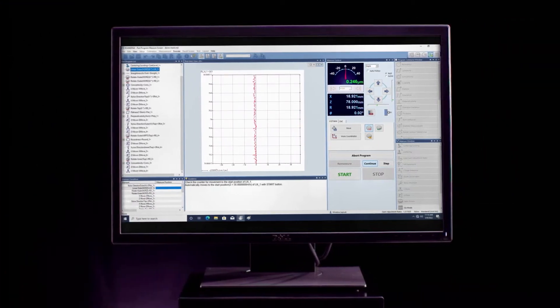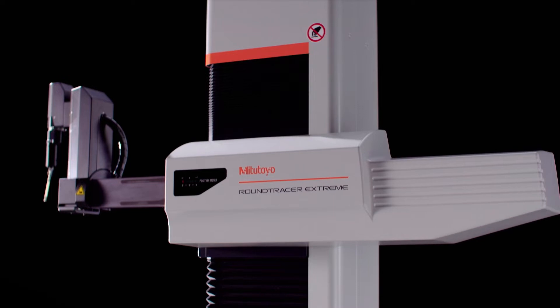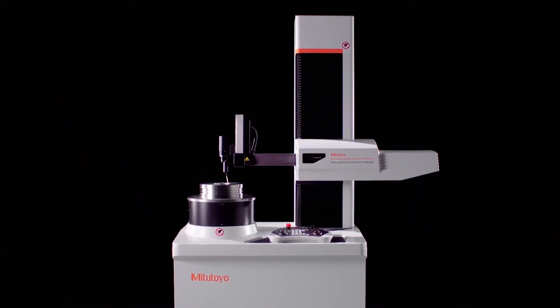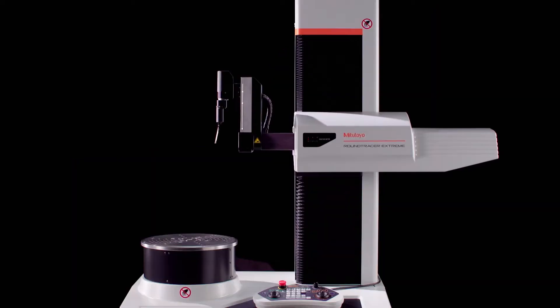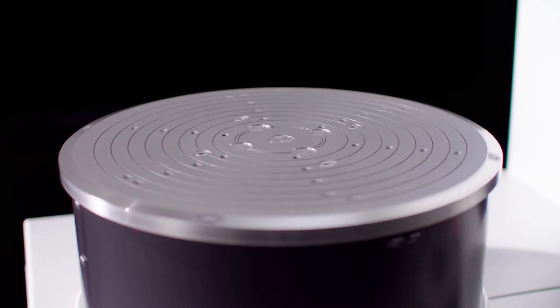Measurements of outside diameters and small holes are efficiently measured. The RTX Round Tracer Extreme features best-in-class positioning speeds with a maximum drive speed of 100 millimeters per second in both the column Z axis and X axis and 30 RPM in the rotary axis.